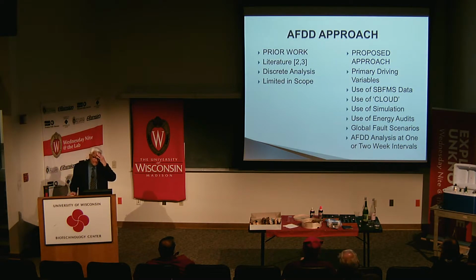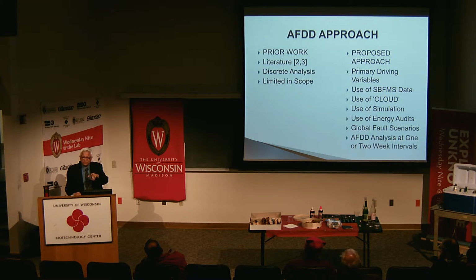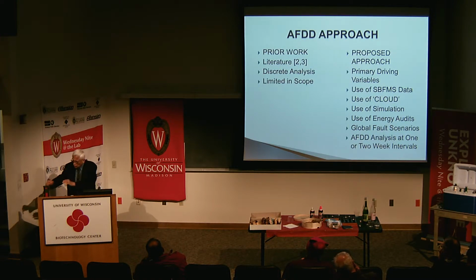Another interesting thing I had in mind is commissioning. Once the commissioning is done, that means you are certifying the building: all the systems and all the components are functionally okay, and performance-wise they behave all right. So if that is the case, with automatic fault detection and diagnosis for new buildings, when you take charge of a new building, there is no need to do it every minute or every hour. You can probably do it once every two weeks for new buildings. For existing buildings, which are older, probably you need to do it every week. For new buildings, every two weeks. For existing buildings, every one week. Not the control loops.